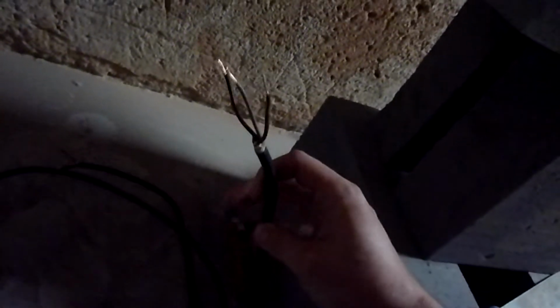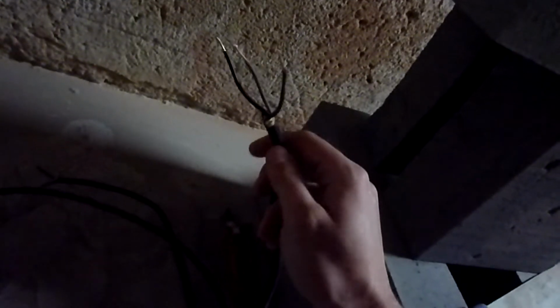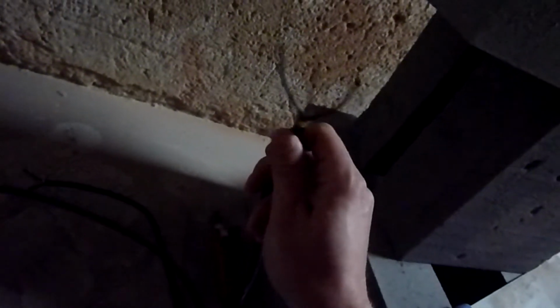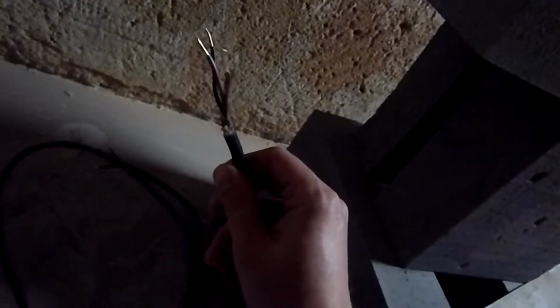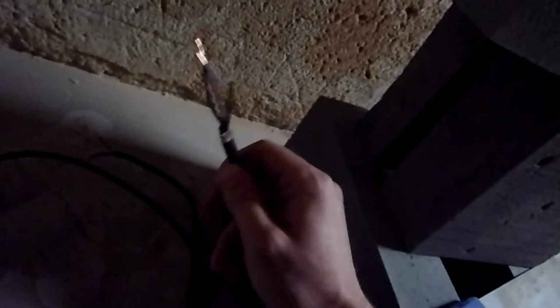You may use some older cable which might be pinched, or somebody driving over it, or anything else, and you can always test them before you use them, or even if you already have them in the wall, you can test it. All electricians must test new installations anyway, but you can also double check if you have insulation resistance testers.